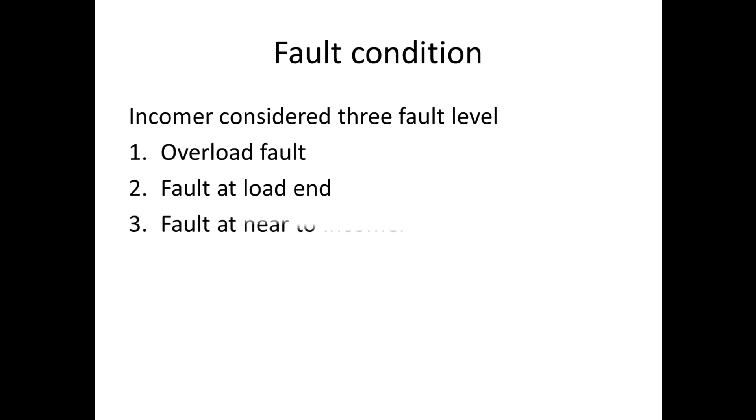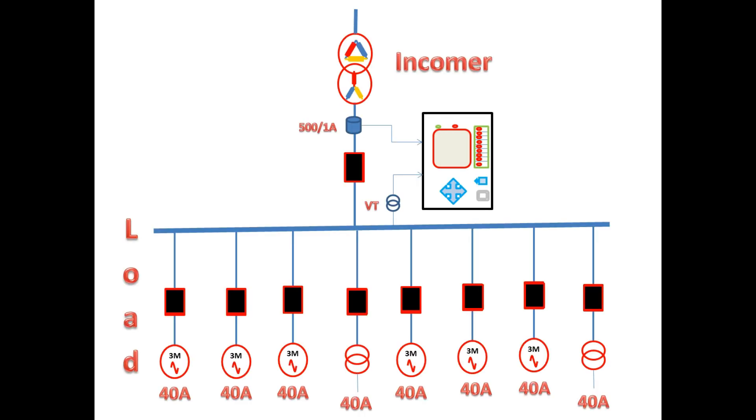First we will see the fault at overload condition. Now the full load current in this feeder is 320A. According to the CT ratio, the secondary current is 0.64A. So I am going to keep overcurrent low stage pickup on 0.68A and trip time is 5 seconds.